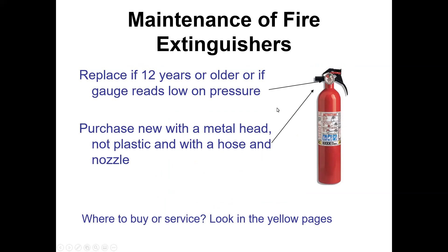For maintenance: if the extinguisher is 12 years or older, or the gauge shows low pressure, just replace it. Purchase one with a metal head, not plastic — plastic-head extinguishers can never be recharged. Recharging is probably not cost-effective; it's better to just buy a new one. The 3A 10BC I recommended is about $40 at Ace Hardware. For servicing, there are companies in the yellow pages, but again, it's not cost-effective.